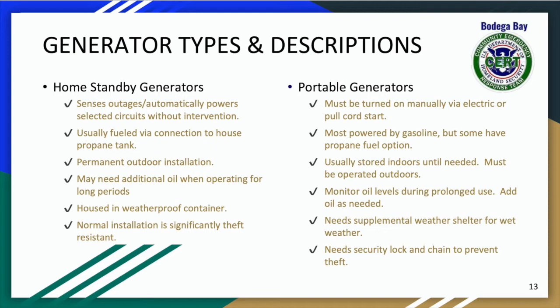You predetermine what you want to turn on with the power you have on those home standby generators. They're installed by electricians and usually fueled via a connection to the house propane tank nowadays. Some people do have diesel tanks. Gasoline isn't normally used because it tends to go bad, whereas diesel and propane last much longer.